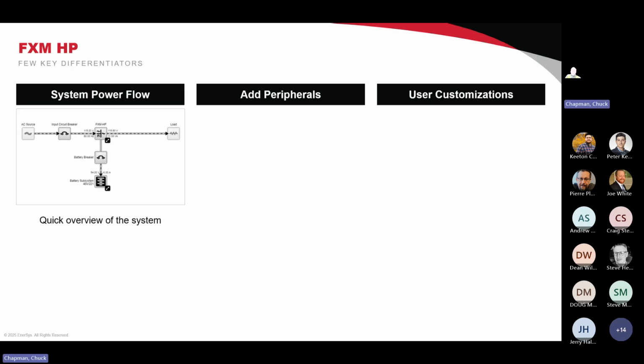There's another really cool display I have called the System Power Flow. This is a real-time running display that shows you the input voltage, the input circuit breaker position, the input voltage to the inverter, the output voltage of the inverter, the load on the inverter, and the battery situation - the battery breaker situation. It shows if it's charging or discharging the battery, and how much and how fast. All of that is shown in this power flow.